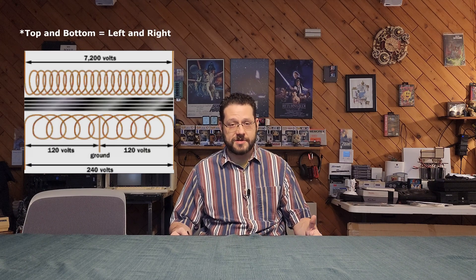Inside your breaker box, you'll likely see some breakers occupy a single slot and some occupy two. The ones that occupy two can have one lever off to the side, or two levers joined by a bar so they flip at the same time — these are double pole breakers. Coming into your home from the transformer are three big cables. One is called the center tap because it comes from the center of the secondary coil of the transformer. The secondary coil is split into two halves, turning 240 volts into two opposing phases. The simplest way to understand this: center and top make 120 volts, center and bottom also make 120 volts, and top and bottom make 240 volts. In the breaker box, the bus bars connected to those cables alternate fingers from either side, so every other breaker slot is on one bar and the ones between are on the other. This way you can use two sequential slots to create a 240 volt line where you need one — usually for an appliance like a furnace or other heavy-duty equipment.